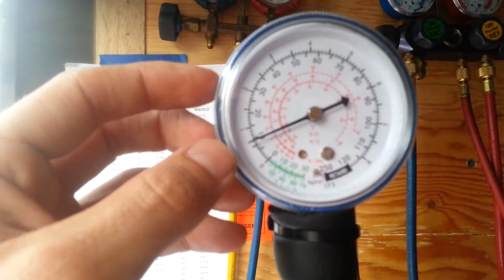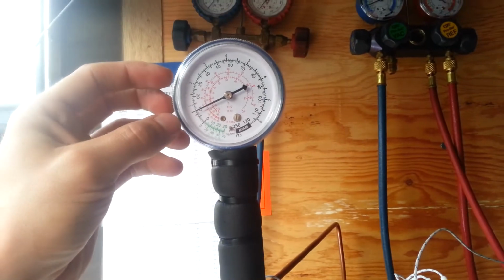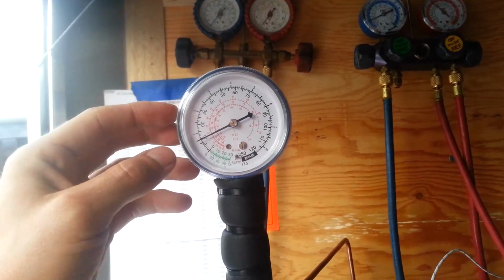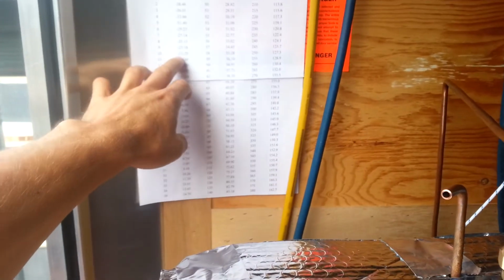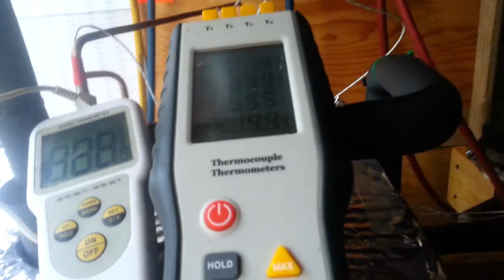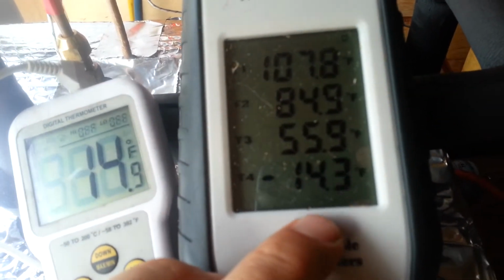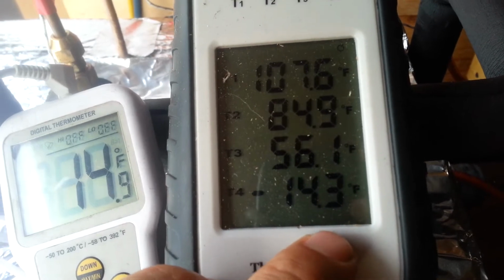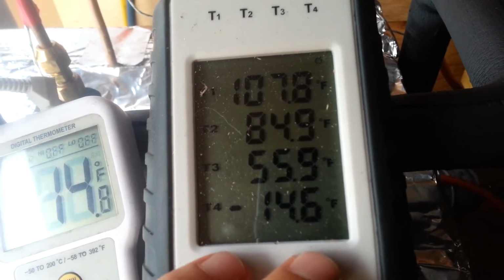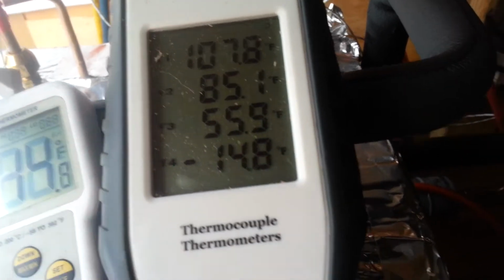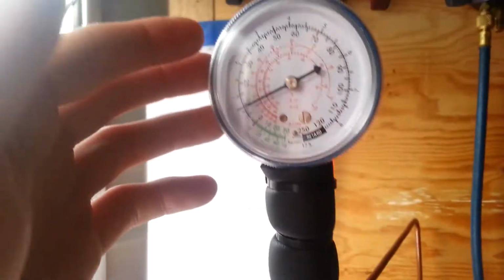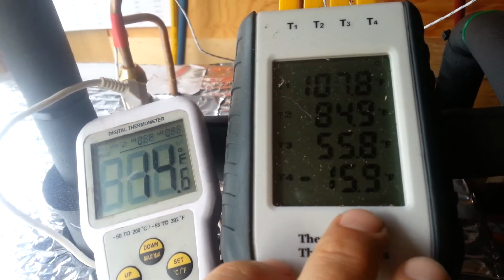So let this stabilize a little bit, and on the suction side, you see it's about -10 pounds per square inch, which corresponds to -21 degrees Fahrenheit. And you see our suction temperature, back pressure temperature, whatever you want to call it, -15 degrees Fahrenheit. Now at these lower pressures and lower corresponding temperatures, the number doesn't track so well.